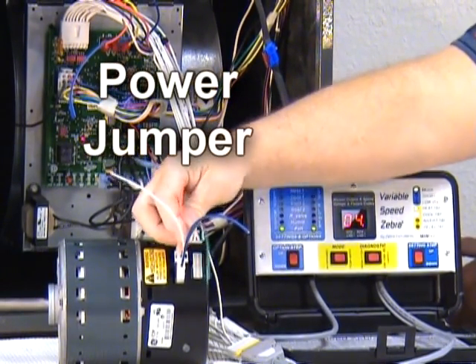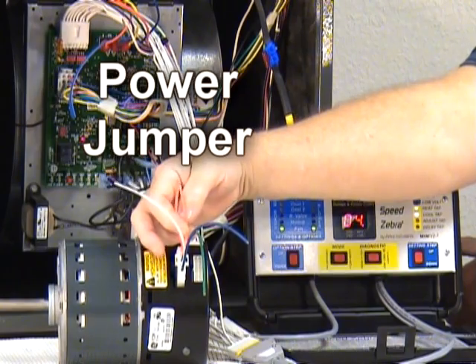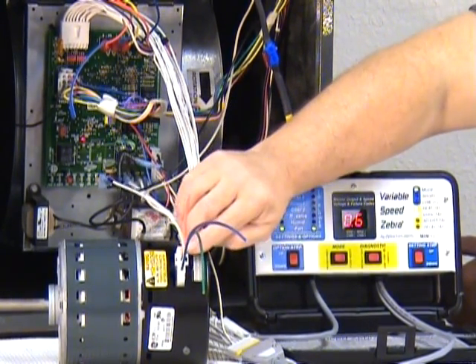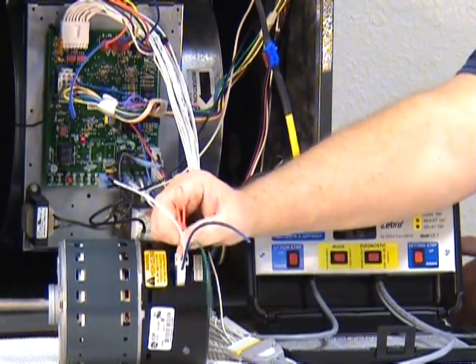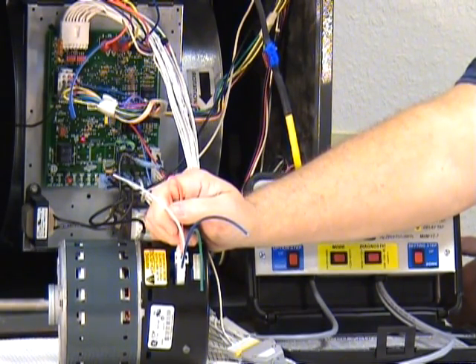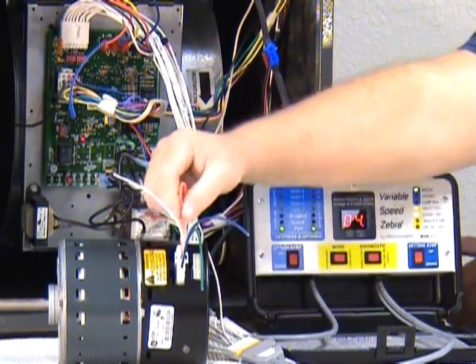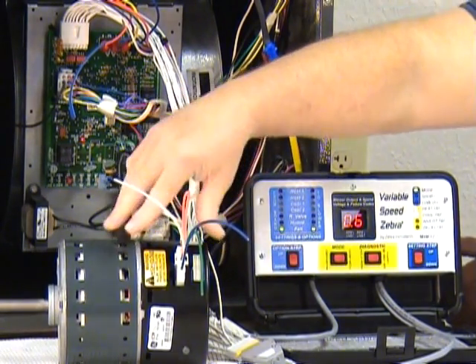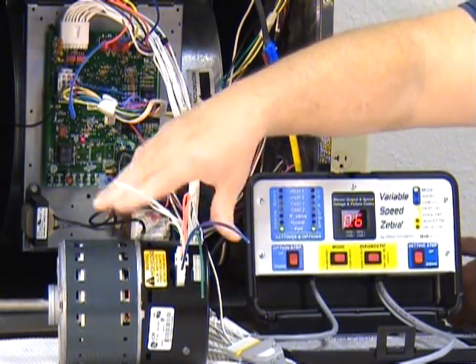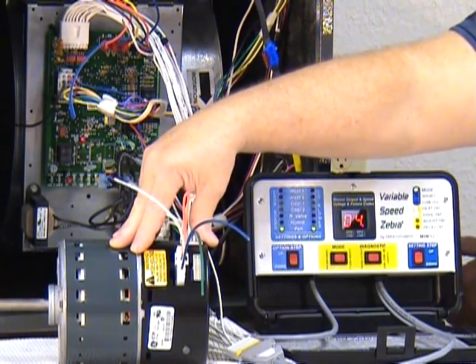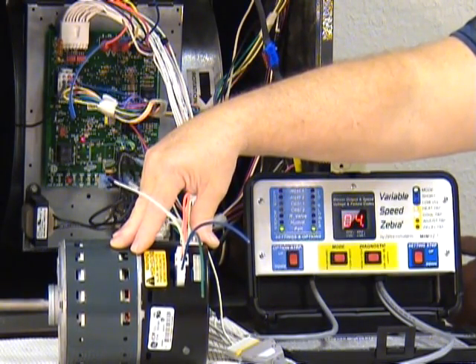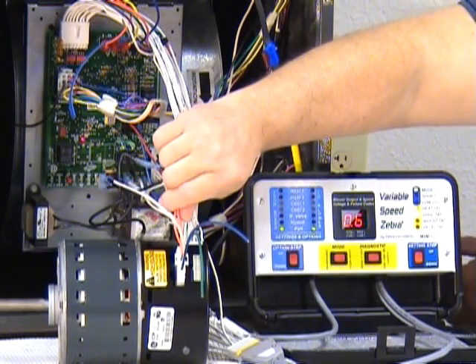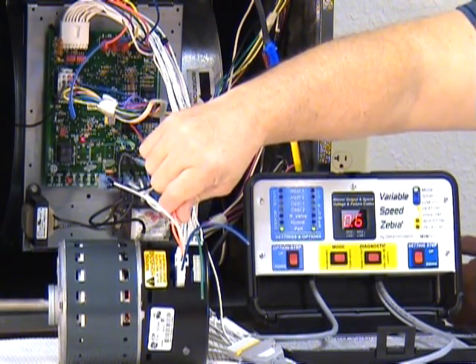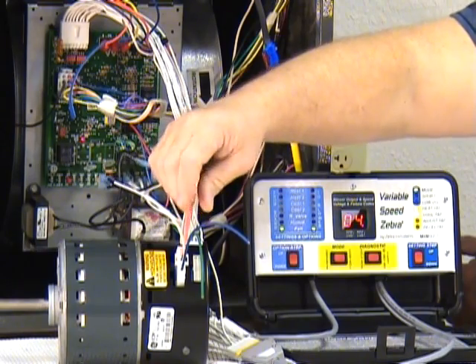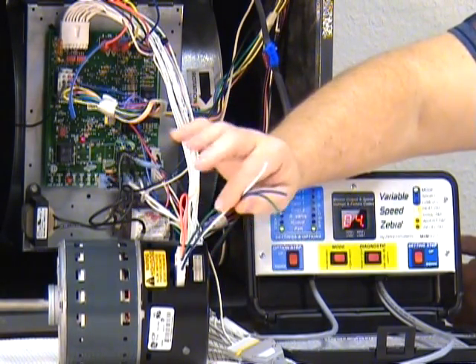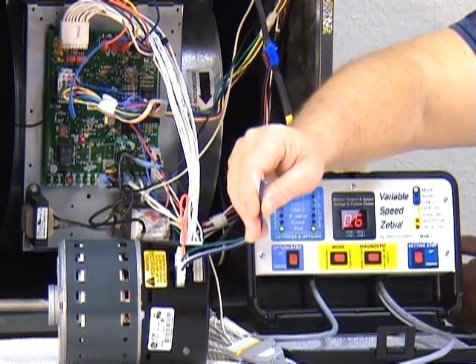By the way, if there's a jumper on this particular power connector, it goes out the 4th and into the 5th pin. That tells you it's a 120 volt configuration motor. If you have a jumper on there, that motor has to be running at 120 volts. Every ECM motor can be either 120 or 240 volts. If it has a jumper, you have to be running at 120 volts. If you have a jumper on it and you plug it into a 240 volt system, you'll burn this module out.